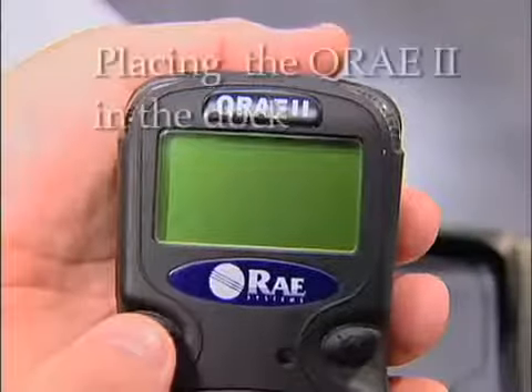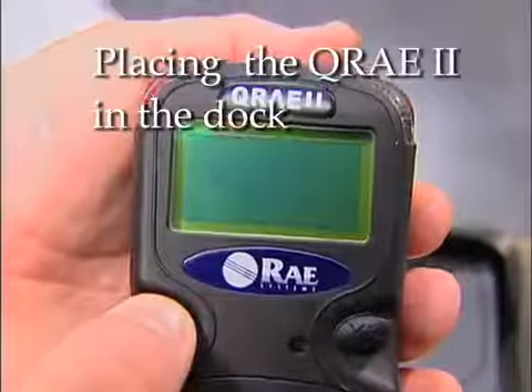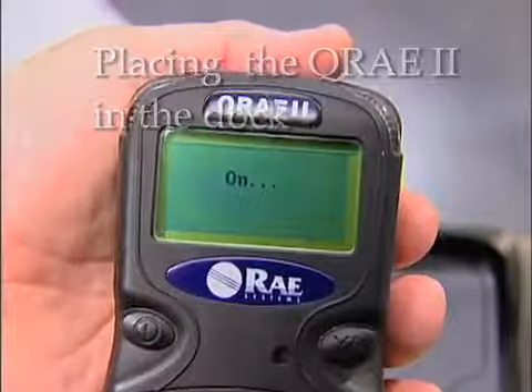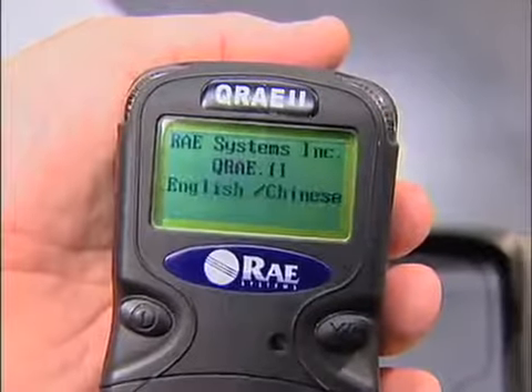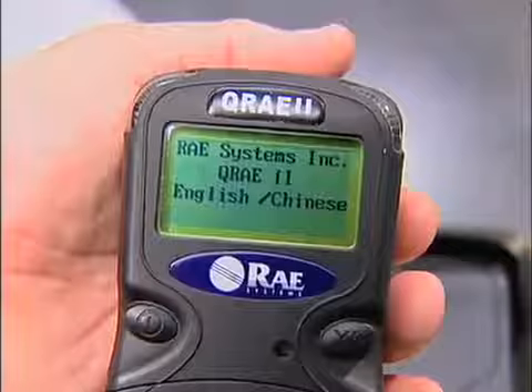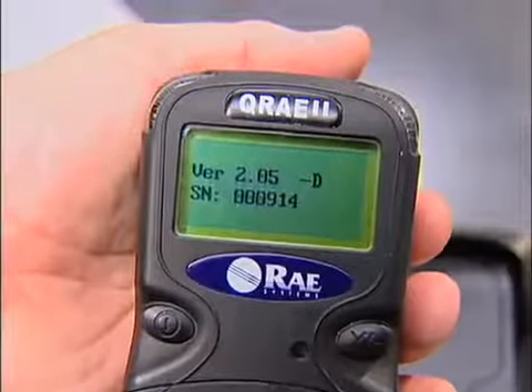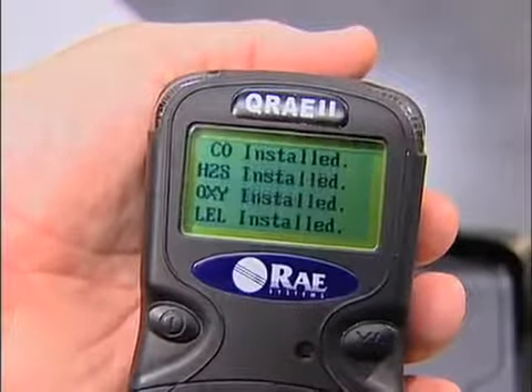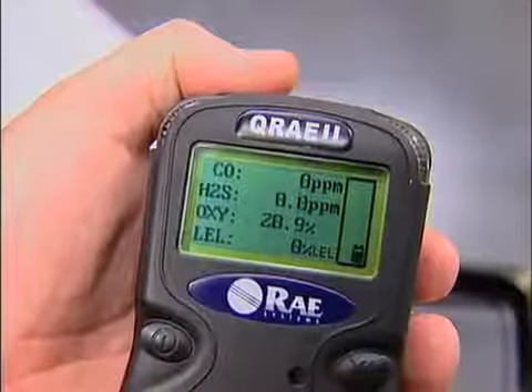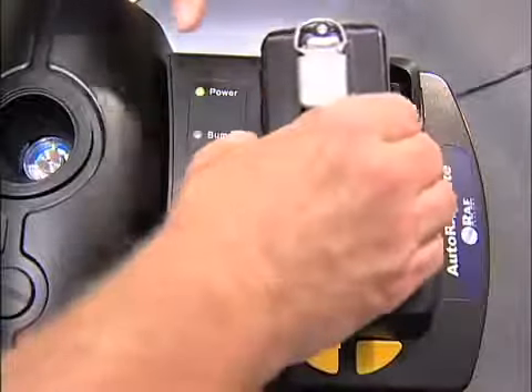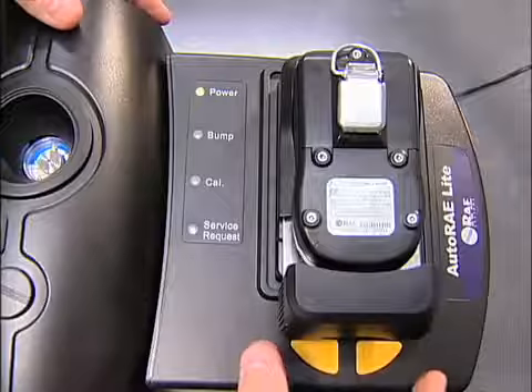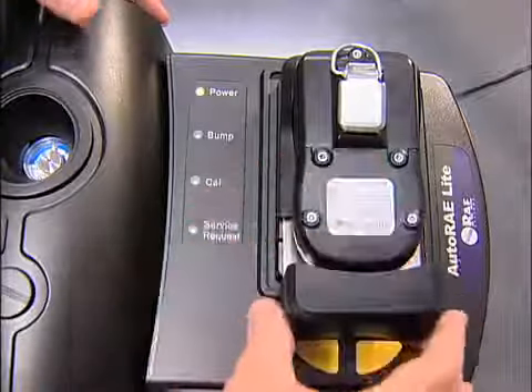Turn on the QRAE II by pressing its mode button and holding it down. When its alarm beeps and characters are shown in the display, release your finger. After the QRAE II has started and displays a reading, firmly press the QRAE II face down in the dock of the AutoRAE Lite for QRAE II. Make sure the QRAE II is firmly seated in the dock.